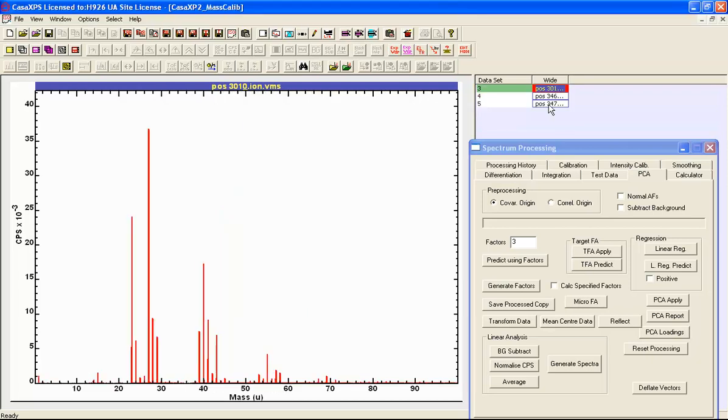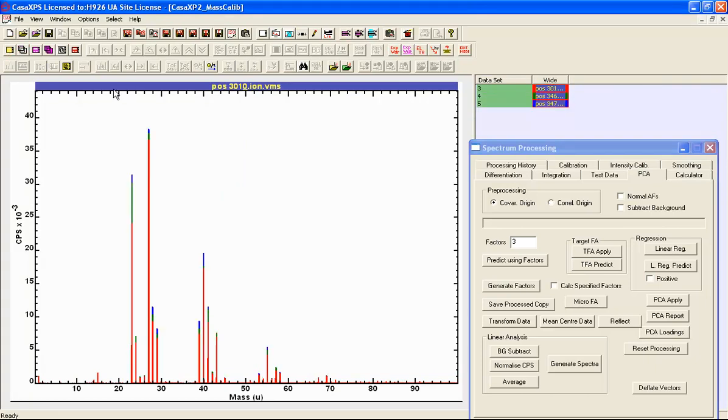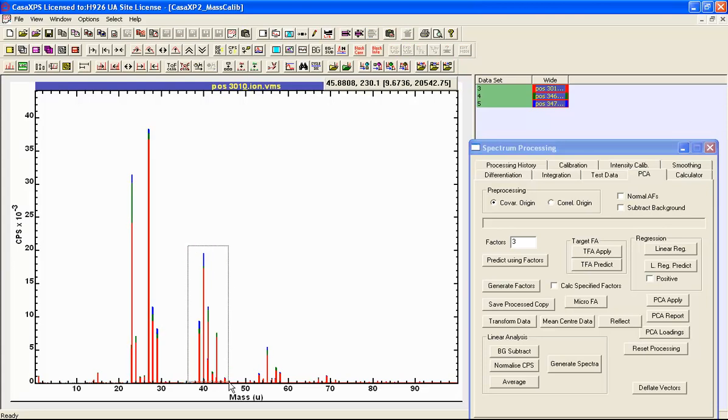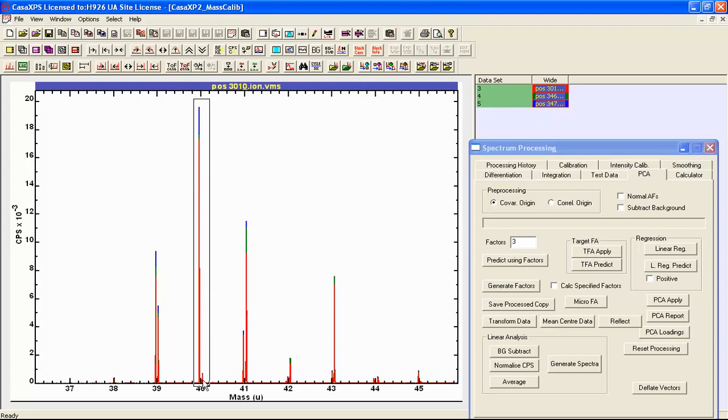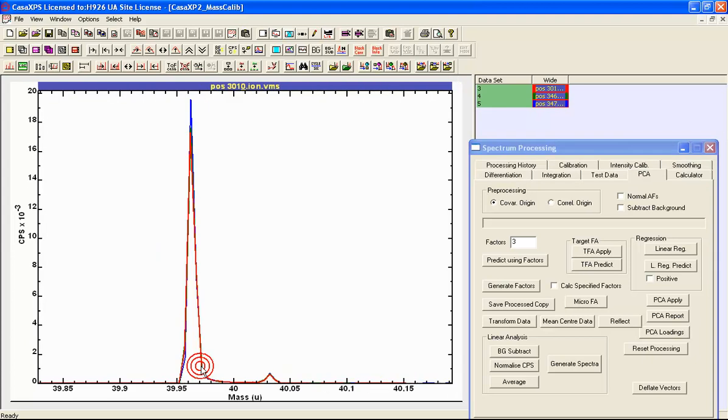So when I press okay, these time bins will all be converted into a limited number, 20,000 mass bins. The three spectra that were previously displayed as time bins are now overlaid as mass bins. You can see one of the consequences of the limited number of mass bins is that the resolution that you see here is far worse than you would see in the time bins. But in terms of displaying the data, this will be helpful.